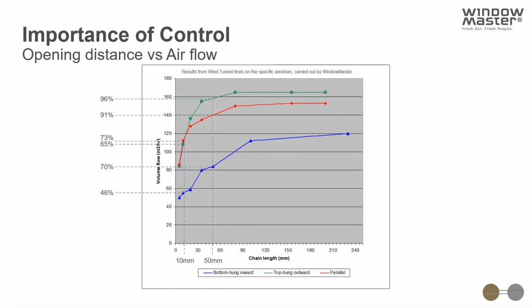Once we've understood that change in demand that we need to track, we also need to consider how air flows through vents. We carried out some research a number of years ago at the BRE using Velfac windows. Here you can see the test results, and it's probably best to focus on the top hung outward opening window, the green curve. At the bottom left there, you can see the results in a closed position at 0, and on the bottom scale, it's the opening distance or the chain length of the actuator in different positions of opening. On the left there, you can see the volume flow rate of air with a typical wind speed applied to it. You might expect a linear scale, so as the vents close, then you would expect no airflow through it, and as you open it, it would linearly increase the amount of airflow through the vent.